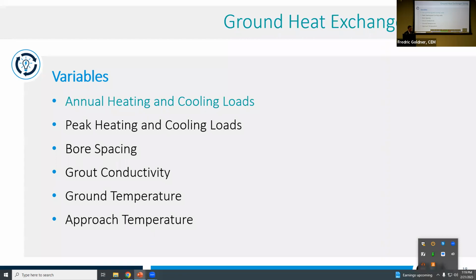Bore spacing, I mentioned, I don't like to go less than 15. You're allowed to go as close as 10. 20 feet separation is the sweet spot. And the reason is just the interference of each borehole with one another. The rule of thumb is the ground is always the eye of the needle, okay? The ground can only give up energy and absorb energy as fast as it can. Okay, you can't expect any more out of the ground. So do not design your system that will exceed the capacity of the ground.